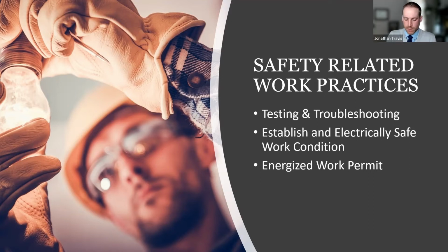So the permit basically says, as a qualified electrical worker, I've identified this job that I could do de-energized. However, there's another reason I cannot de-energize it. You take that to your manager or safety manager, whoever approves it, and they have to agree with you. Or it could be the other way around. The person requesting the energized work could be the manager or the supervisor, and the qualified electrical worker needs to agree. Yep, I'll do it. That's what the permitting process is for, is to make sure that everybody's on the same page.